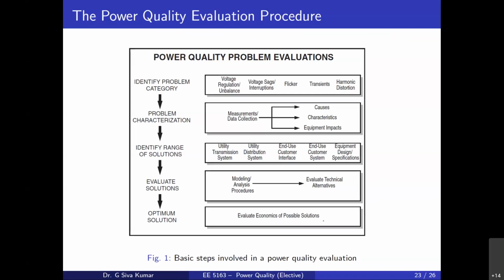Think it over. What I feel is it all depends on what the voltage will be at this particular point. For that we need to look at the entire system. If the voltage is well within the limits of 0.9 to 1.1 per unit, giving a solution at this point is not appropriate. Also, the cost is much less when you provide the solution at the far away point.